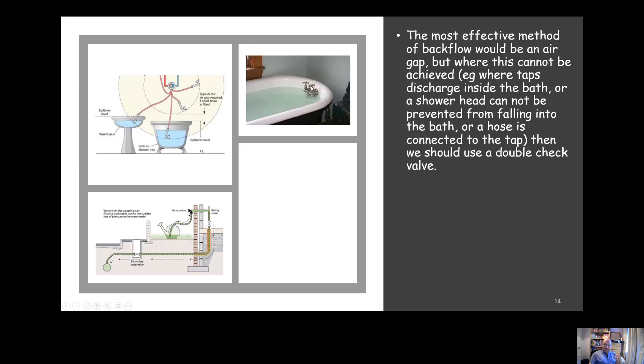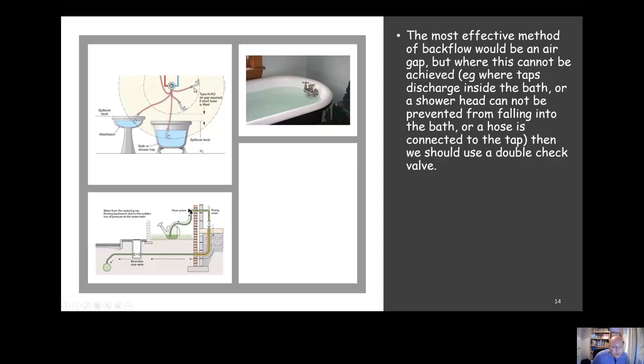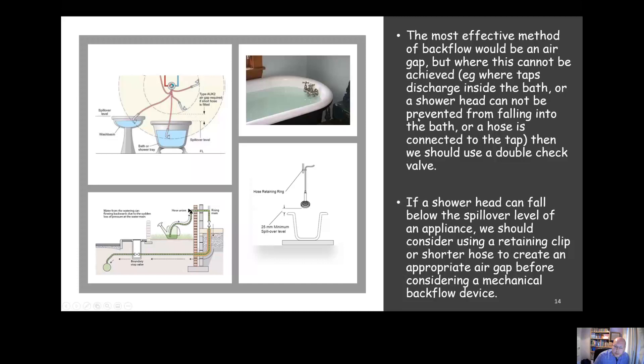Where bath taps are discharging inside the bath below the spillover level — as shown in the picture — we can't achieve an air gap, so we need to use an appropriate backflow prevention method: in this case a double check valve on both the hot and cold to prevent category three bath water being drawn back into the pipe. Where there's a shower head in the bath, there are various methods to maintain an air gap — for example, using a shorter hose or a retaining clip to give an appropriate air gap.